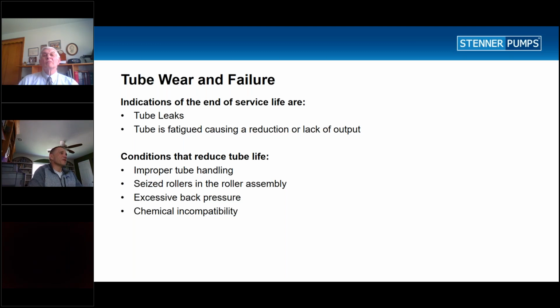So tube wear and failure. A few things that will cause that is lack of service to the pump head. So if you do have a leak, and I see it on a tube, and you replace the tube without cleaning out the pump head, what that'll do is possibly hang up the rollers, and that'll lead to excessive tube wear. Not handling the tube properly.